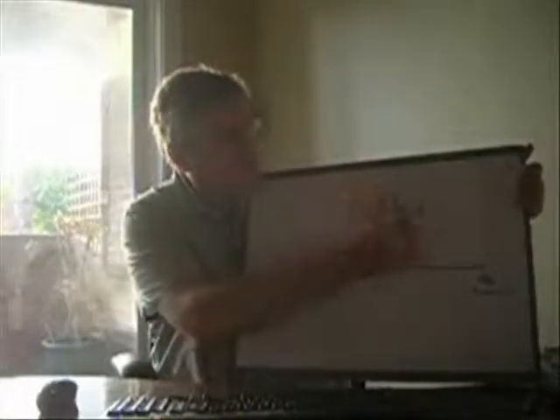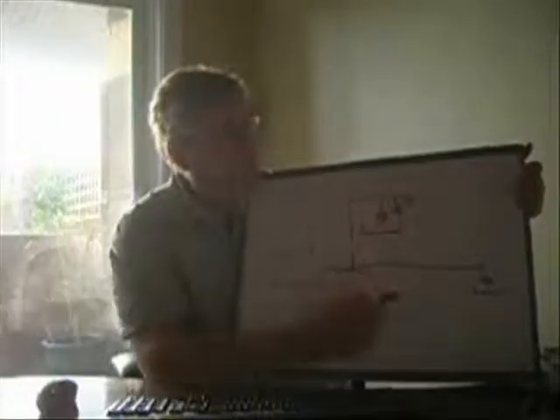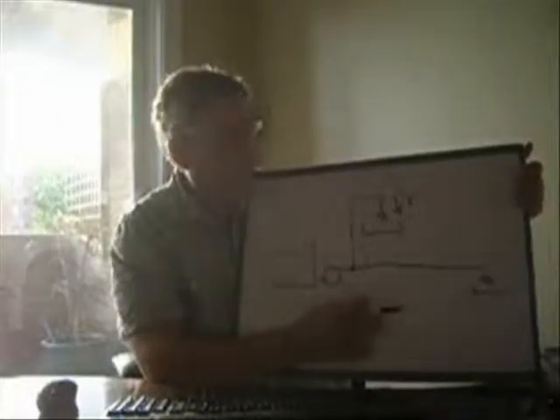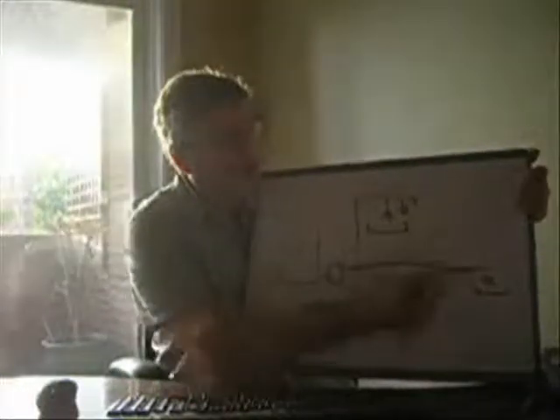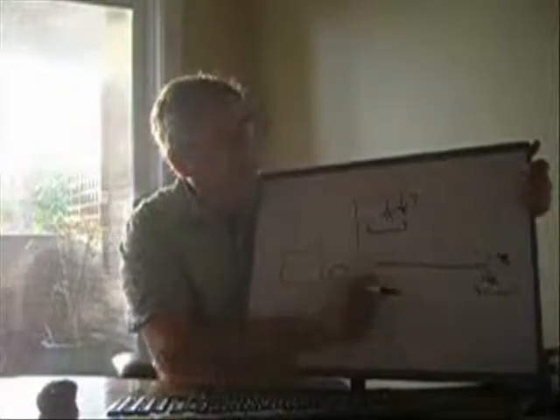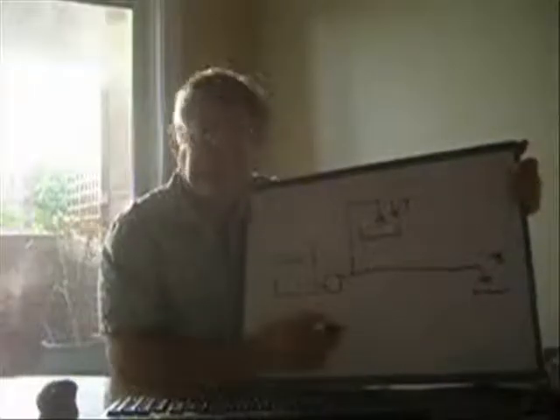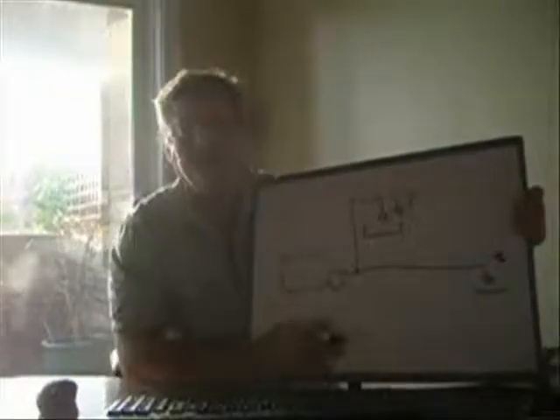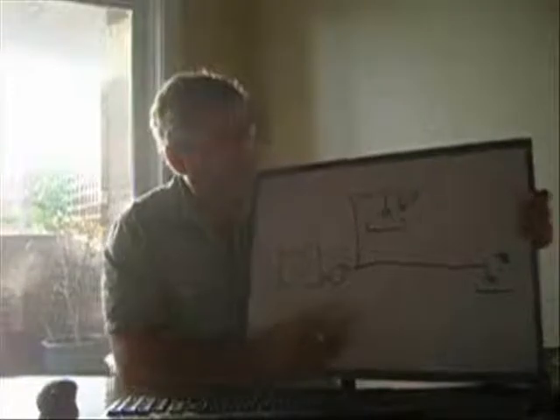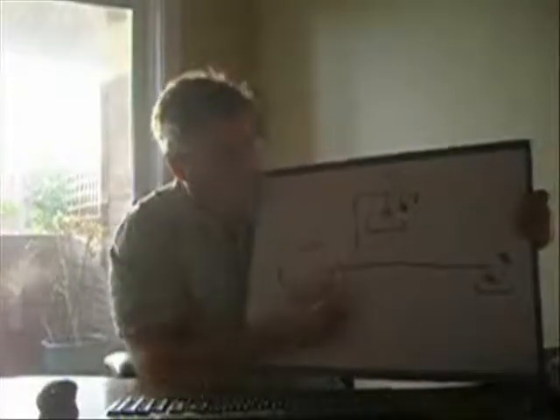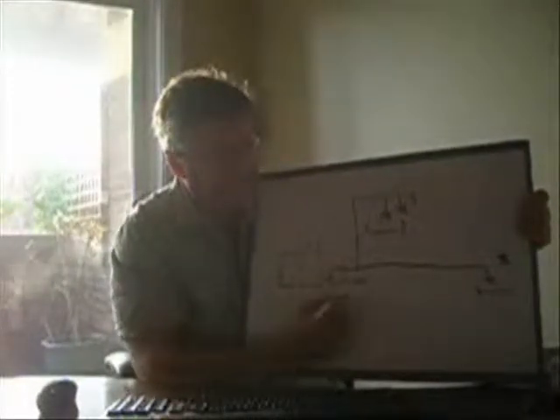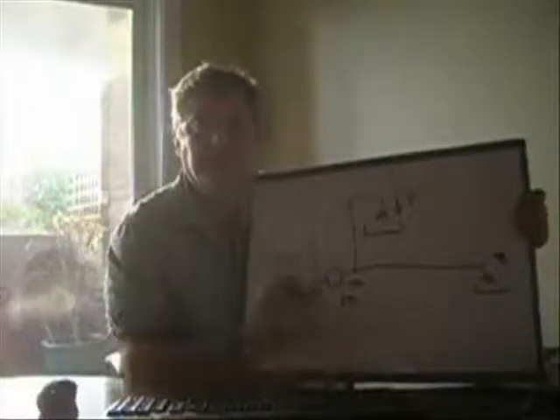We know, first of all, we're going to set the flow rate of the shower. Let's say we set the flow rate to seven gallons a minute. And this consumer down here, even though it's further away, let's set it at three. We would like to get seven here and three here at the same time - that's our initial requirement. So the pump itself has to be able to deliver ten GPM. That's a given.